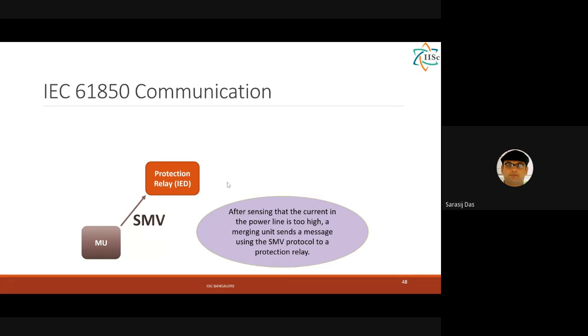The merging unit converts the analog signals into digital. So all current and voltage values are converted into digital values, and then these values are sent to, suppose, a protection relay via SMV protocol. Now, the protection relay uses SMV, which is the sample value message protocol, and using that protocol, the digital samples are sent to relays.